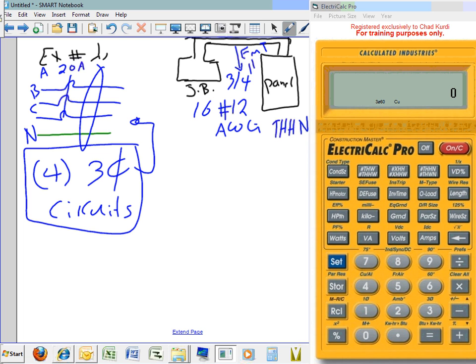So let's see. Now it's a 20 amp circuit. How much can I pull out of this 20 amp circuit through these conductors? There are 2 ways. Number 1, guys, I already decided to use number 12. I'm not changing conductors. I'm going to use number 12. So I need to know how much current can I pull out of number 12.